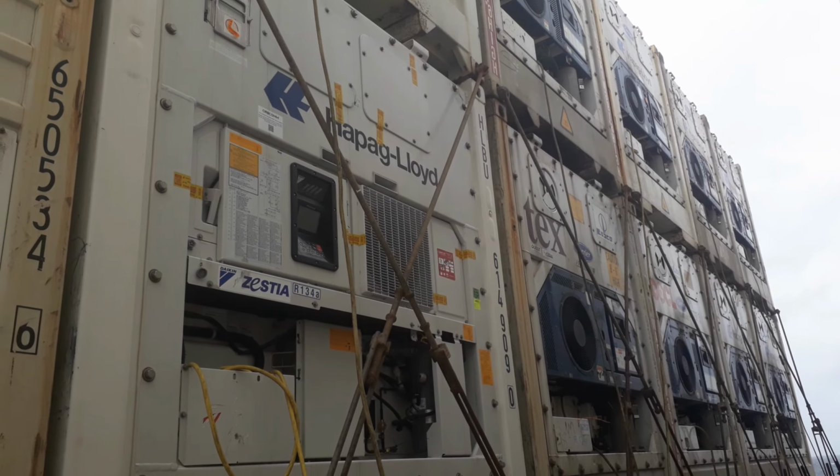And that is to replace a defective compressor unit. But of course, I'm still a little bit lucky that the defective compressor is from a reefer container which is stowed inside the cargo hold. It means that we do not need any staging or scaffolding prior to replacing the compressor unit. It is much more difficult to replace the compressor unit in an open deck stowed above other containers than working inside the cargo hold area.